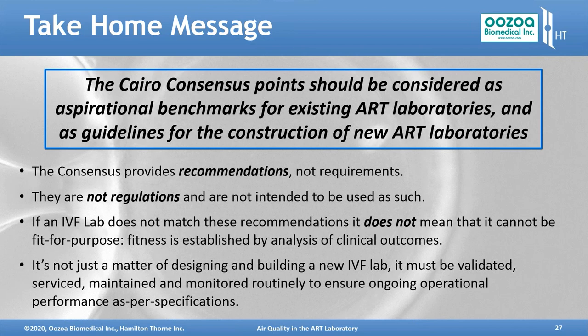It's not just a matter of designing and building a new IVF lab. When you've designed it and you've built it, you've got to validate it. Everything's got to be serviced, maintained, and monitored routinely to ensure that your operational performance on an ongoing basis is as per specifications. You don't just build a unit and say, this is it, it's validated, it'll go forever. It needs to be monitored. If it's serviced and revalidated by an independent third-party company once a year, that's fine.